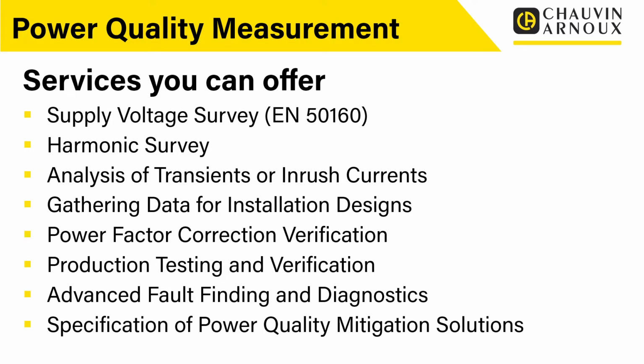Analysis of transients or inrush currents. So one of the things that power quality analyzers are very good at is these quite fast events. So say you were having problems with surge protection, you were having surges, you were getting equipment that was damaged, you wanted to specify some surge protection, but you didn't know what type of surge protection, what levels, what speeds they need to operate at. Again, you could do an analysis of the transients within the installation or within a particular circuit, for example, and actually work out exactly what you needed to protect against and put those protective measures in place.